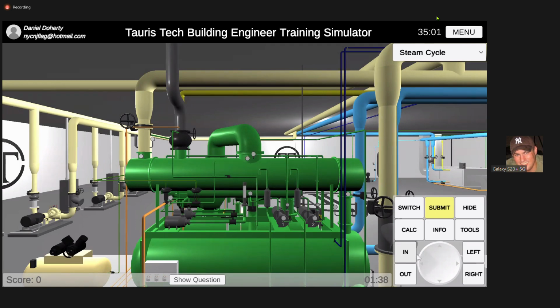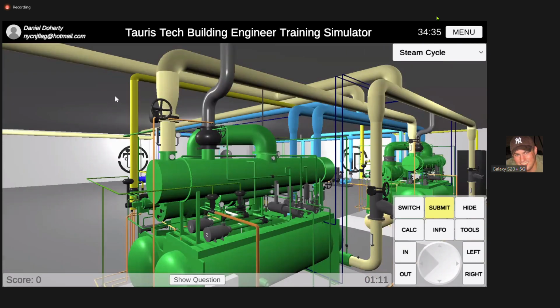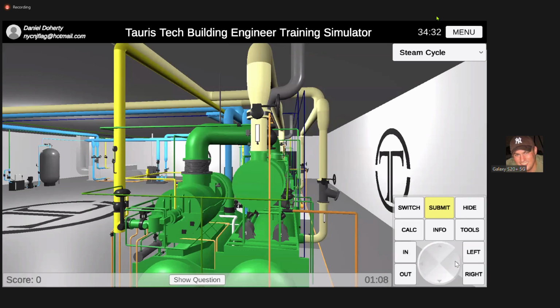You have to maintain water in the hot well because that water actually creates a seal. It's a sealing effect. It's like a vacuum ring seal that you have on your vacuum pumps. You also have a hot well seal. It's in the PDFs that I sent you guys. If you read the PDFs, you can read about this and you'll understand it better than me. All right? But that's pretty much your steam cycle, man. Your steam cycle starts on the header and it ends at the hot well.